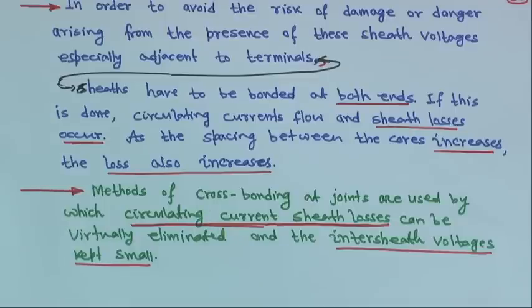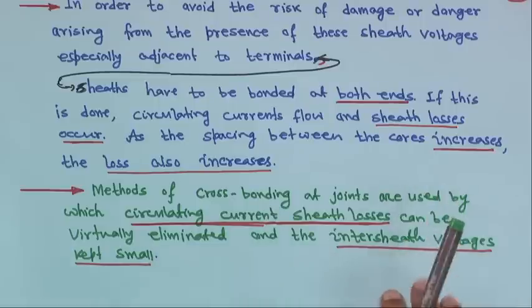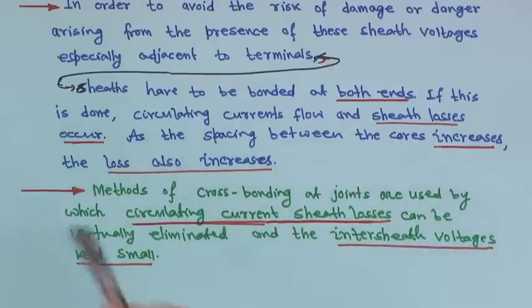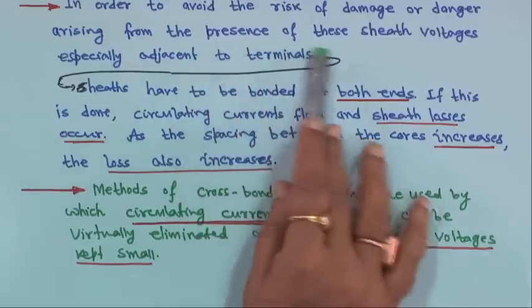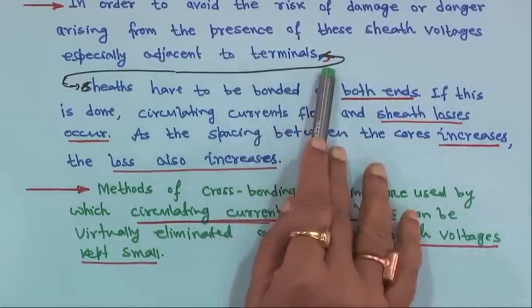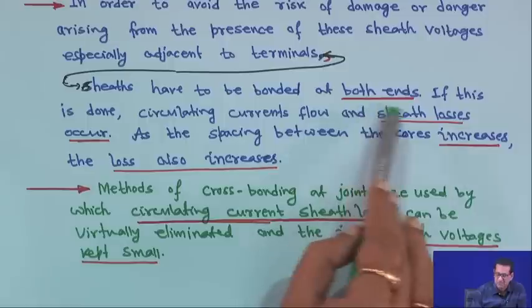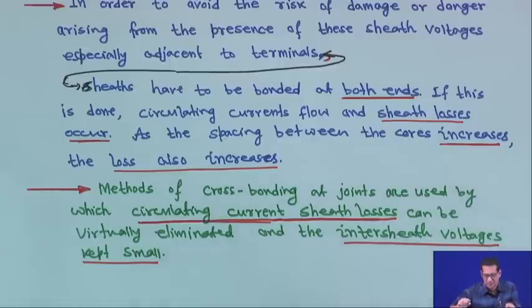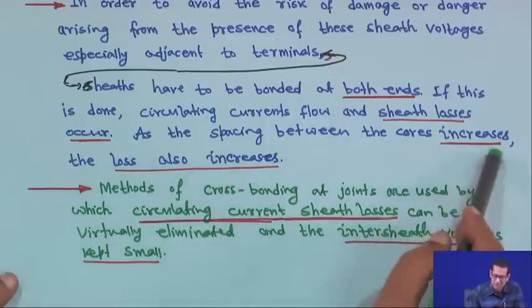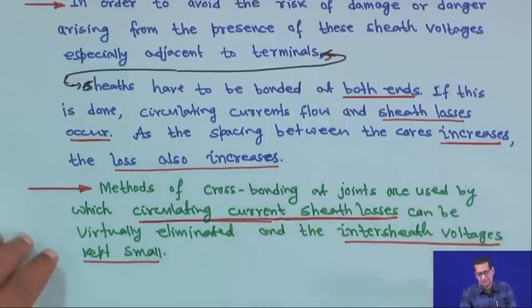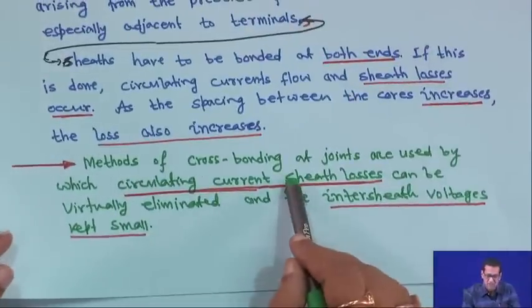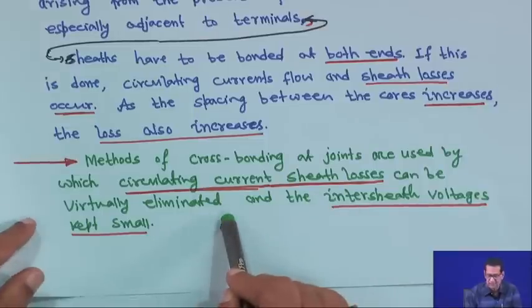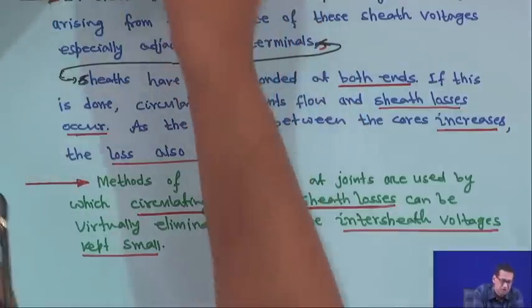By bonding at both ends, we are allowing the circulating current to flow. The sheath, like transmission line transpositions, has to be changed at regular intervals. In order to avoid the risk of damage from sheath voltages near terminals, sheaths have to be bonded at both ends. If this is done, circulating currents can flow and sheath losses occur, but as the spacing between cores increases, the loss also increases. Methods of cross-bonding at joints are used by which circulating current sheath losses can be virtually eliminated and the inter-sheath voltages kept small.